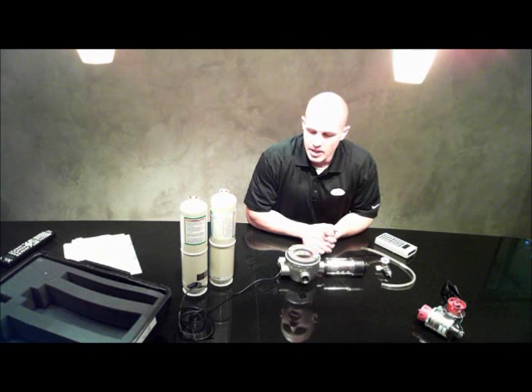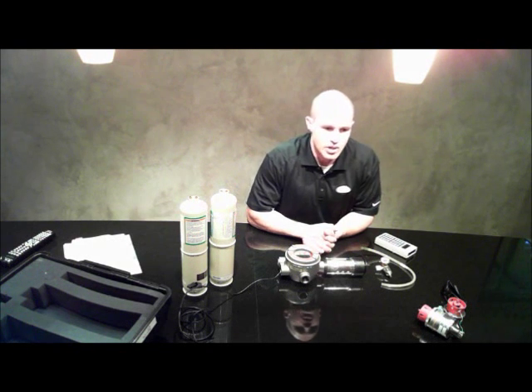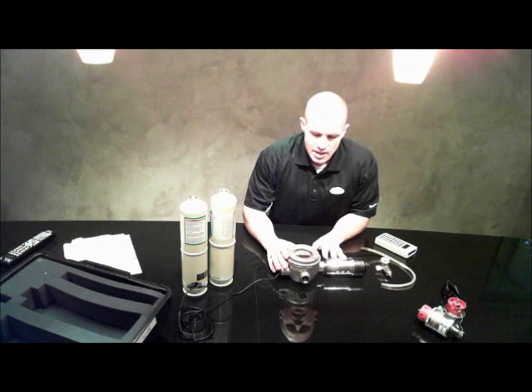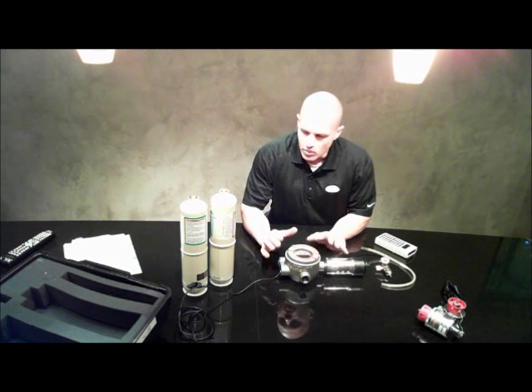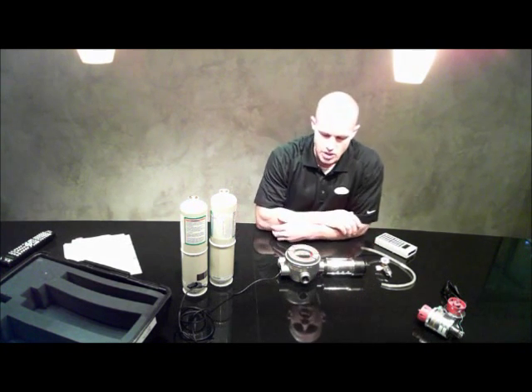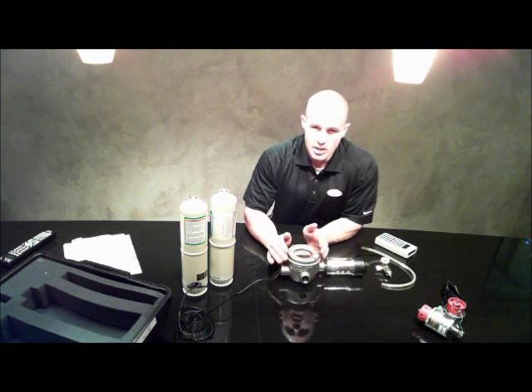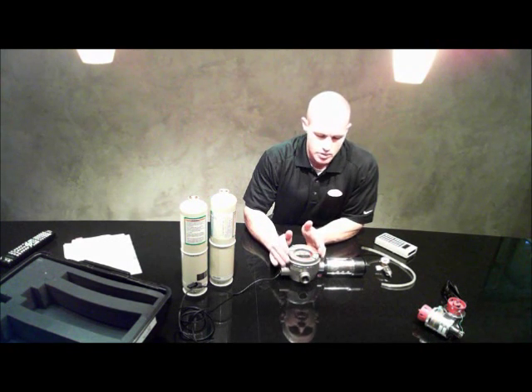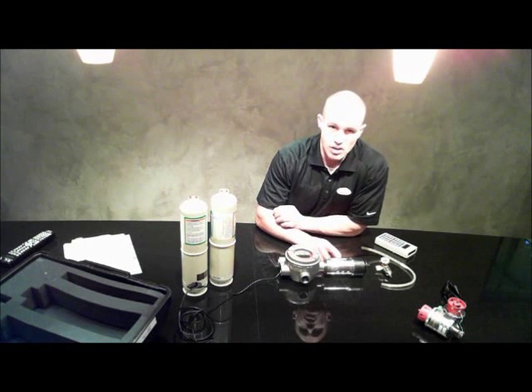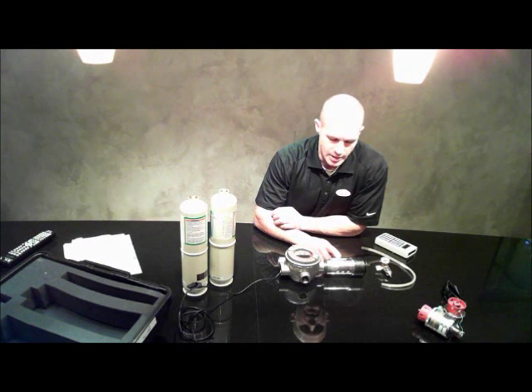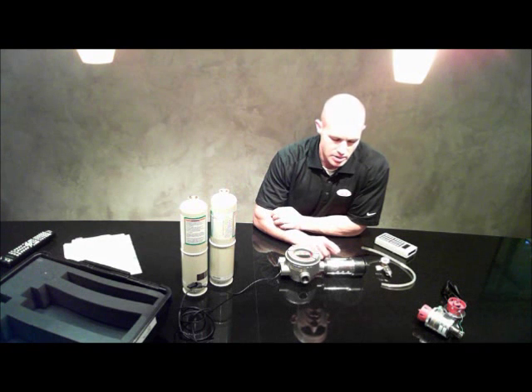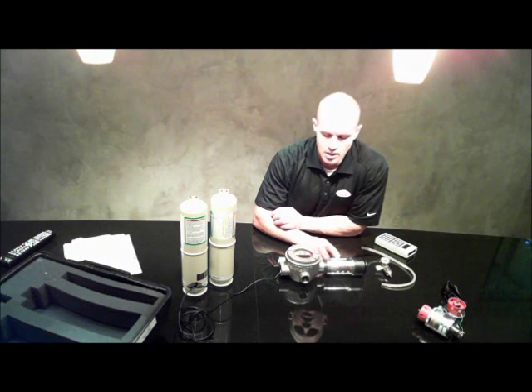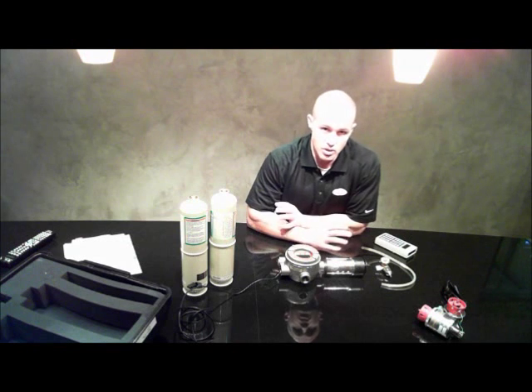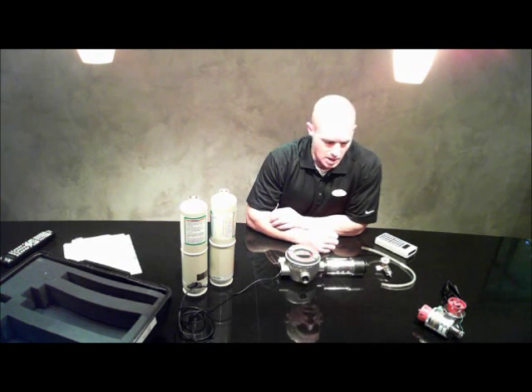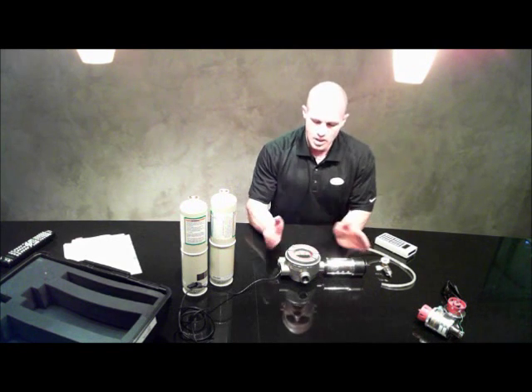What I'm going to do today is show how a calibration is done on an MSA gas monitor. So what I've got here, I'll just give you a quick layout of what's going on. This is an MSA Ultima X monitor, transmitter head here with an integrally mounted infrared sensor. This is for a combustible gas, methane. But the same principles apply across the board as far as calibrating MSA sensors on monitors. So that's what I've got here.